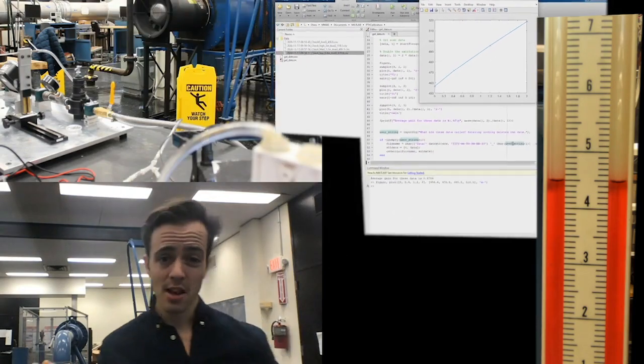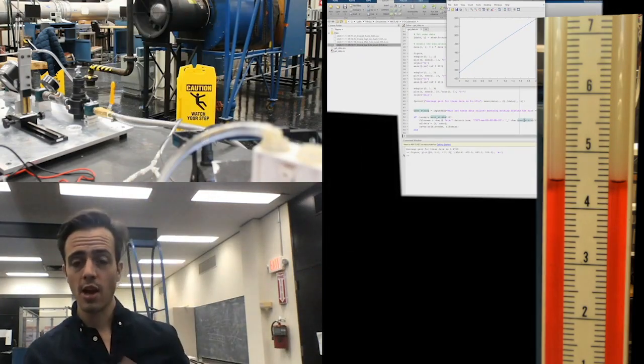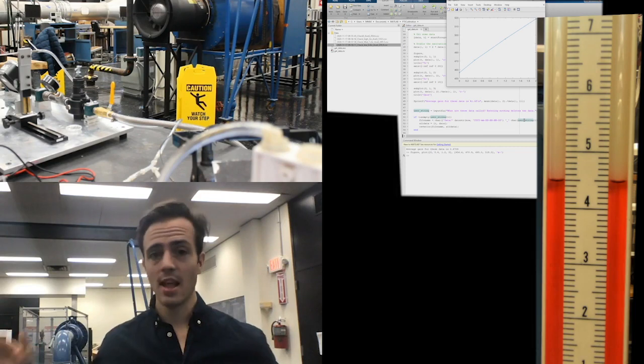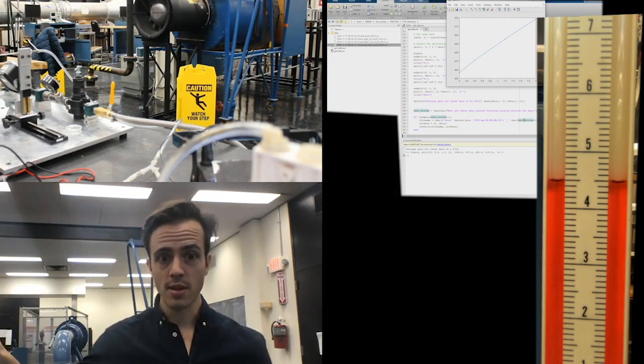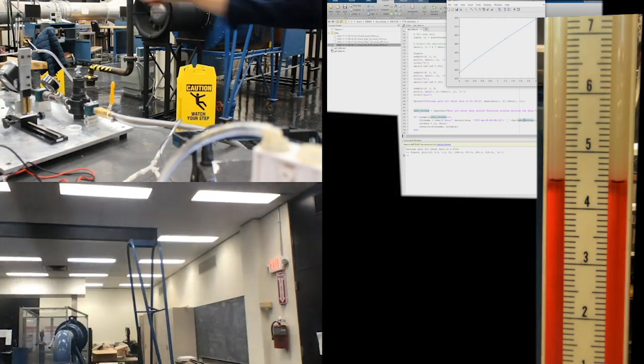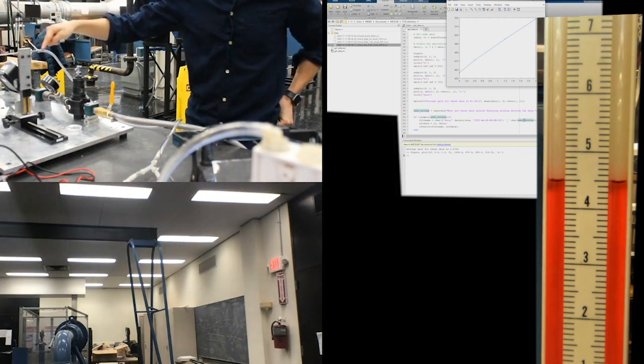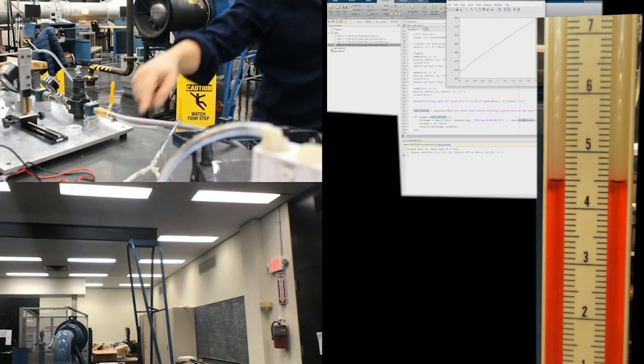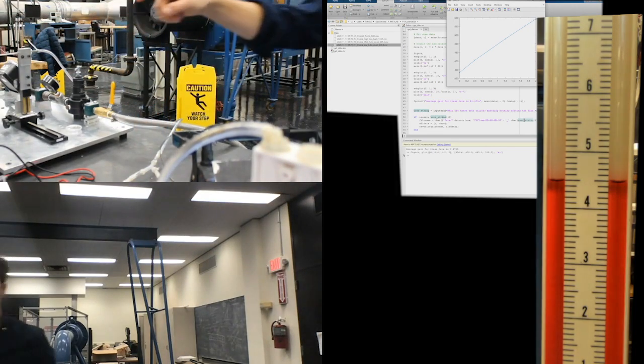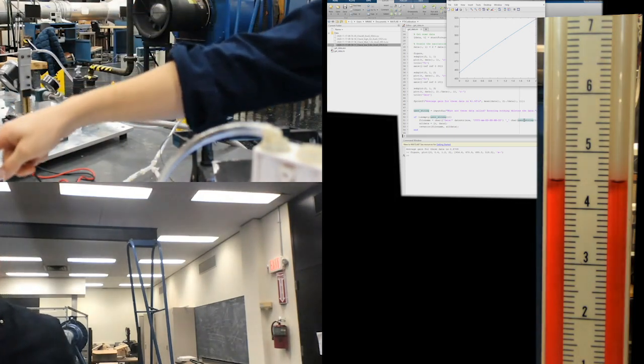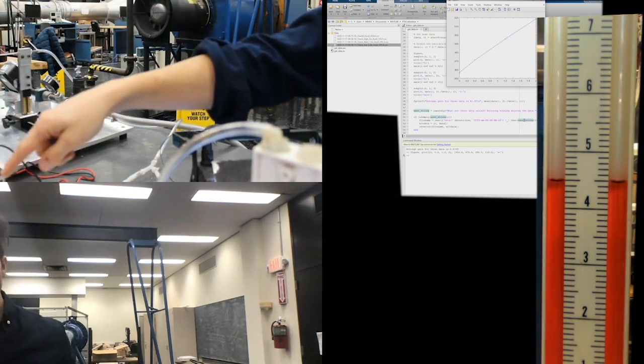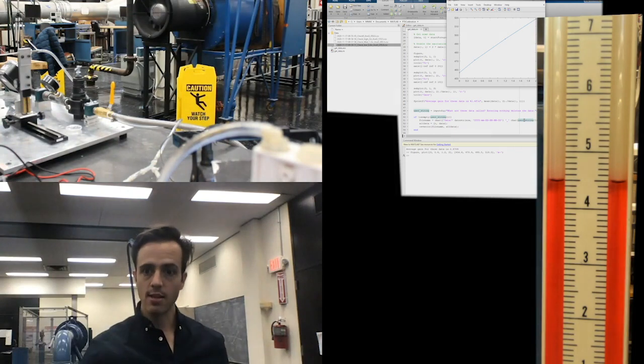We could have done this using an oscilloscope. I just choose to do it using the actual setup we're going to be using, because this tests every part of this measurement system, from the actual output, checking the pitot is working, and getting the data all the way, checking that the manometer is working, and further checking that the excitation is working, checking that my transducer is working, checking that the ADC is working.